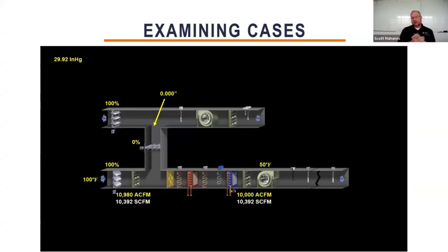So one of the things we've got to understand is when we do comparisons of airflow stations, when they're in different densities, you can't do it volume to volume. The only comparison you can make is mass to mass. So SCFM to SCFM is the only way it works out. Now, if I calibrated this outside airflow station to 10,000 CFM, that would be a 9.8% mistake. So you've got to be careful about how you allocate what you measure.